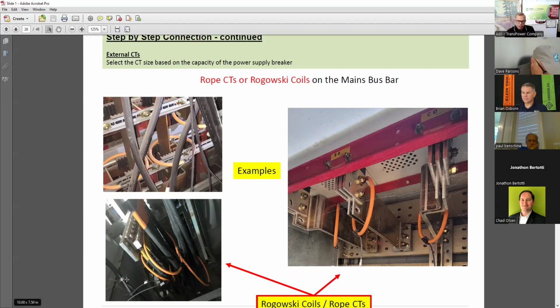You can catch it at the cables. You open the bottom panel of the switchgear, you see the cables connecting to the bus bars, and you can wrap it around those cables. Now, are these the AccuEnergy meter CTs or the MPTS CTs? Both. You put both in the same spot. Both CTs have to be here. Okay, maybe that's what I misunderstood. This is only showing one set of CTs because until last year, or after COVID, we installed only one set of CTs and connected both the AccuEnergy meter and the MPTS to the same CTs, because the same information goes to both meters. So you're saying best practice has been altered to have two sets of CTs, one dedicated to the meter and one dedicated to the box. That's correct. That's the clarification I needed. Thank you.